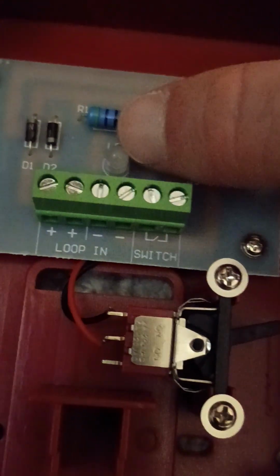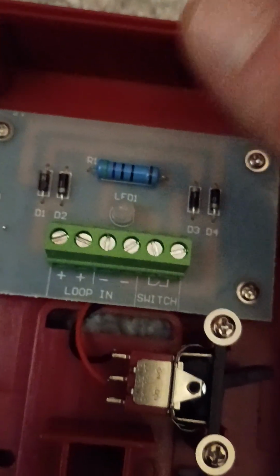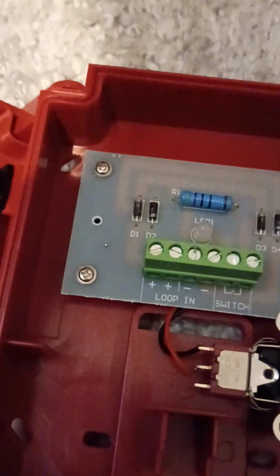When you pull this specific device, this is the only pull station affected. They'll know which one, because the LED shows them, and a lot of newer devices have LED lighting for that reason. The panel will also tell you which pull station was pulled, so they go to that one.